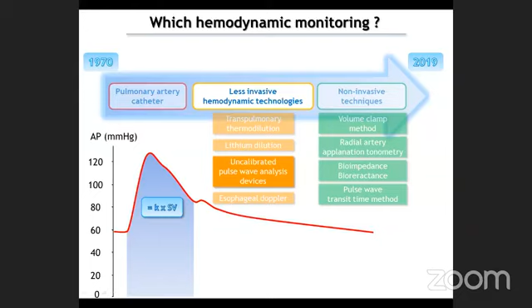Let's move to the uncalibrated pulse wave analysis devices. The pressure waveform analysis estimates cardiac output from the shape of the arterial pressure curve along with patient-specific anthropometric and demographic data. All available devices use the same principle: the amplitude of the systolic part of the arterial curve is proportional to stroke volume and inversely proportional to arterial compliance. The arterial curve is obtained through an arterial catheter, and the devices do not require any external calibration.